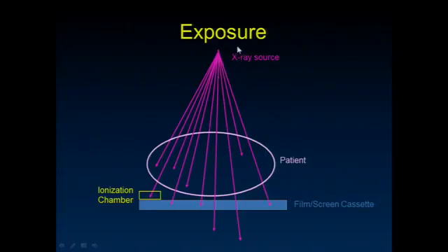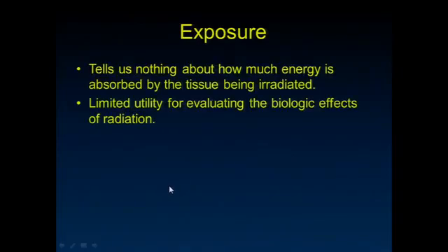Early on, one of the things you did with this was put this between the patient and the film or screen, right? And when it reached a certain level, you could actually shut off the X-ray equipment. It said that you had an adequate level of exposure to that X-ray plate. And so hence the term, right, that why we call this the exposure.